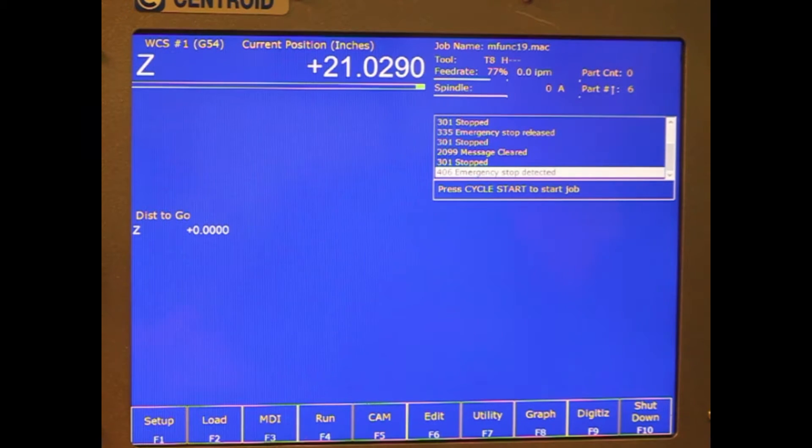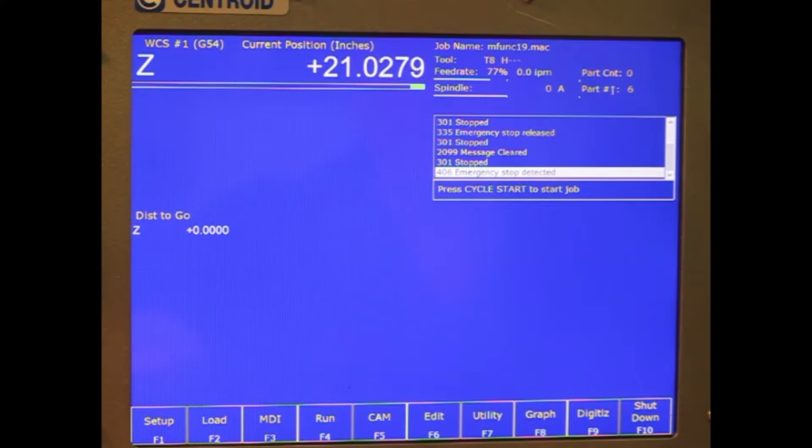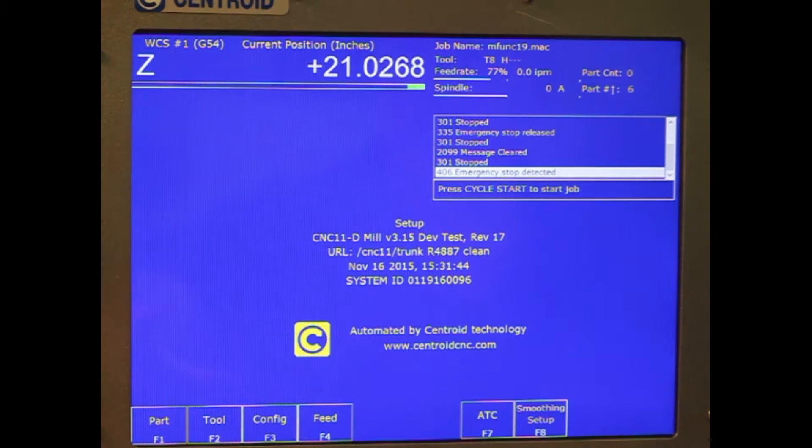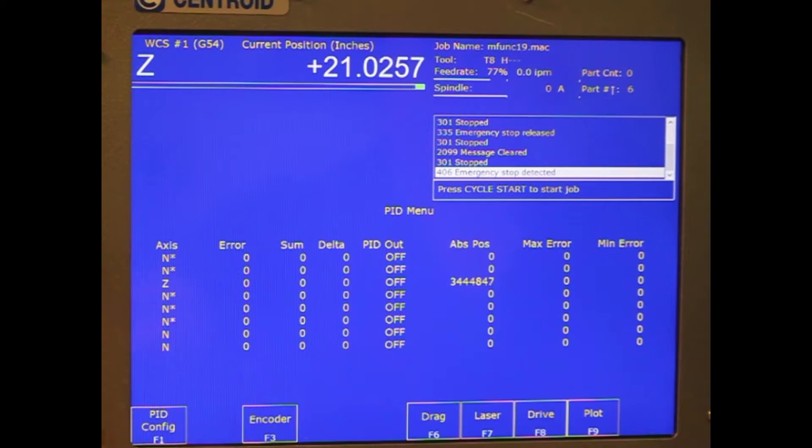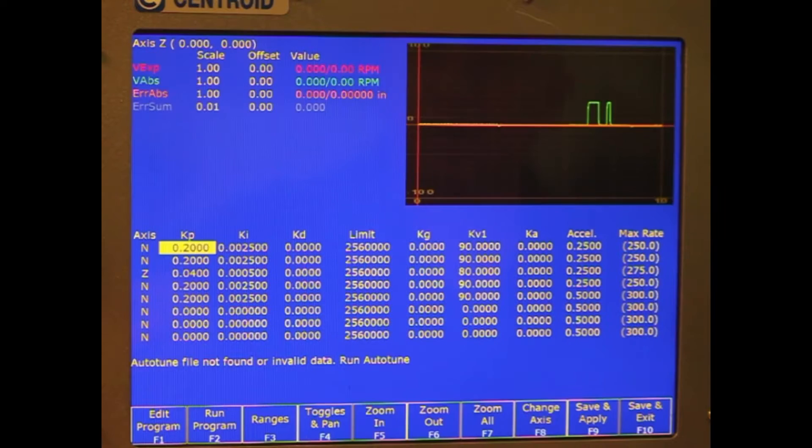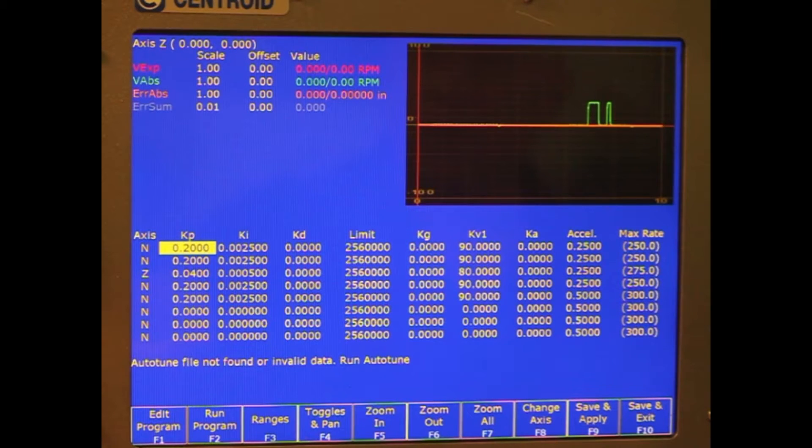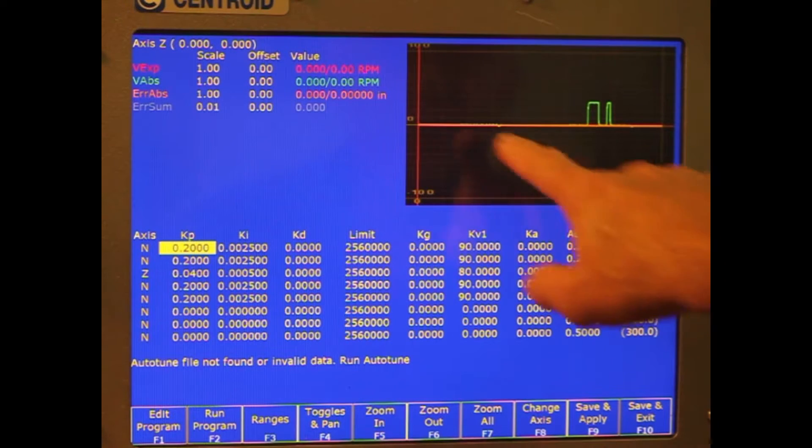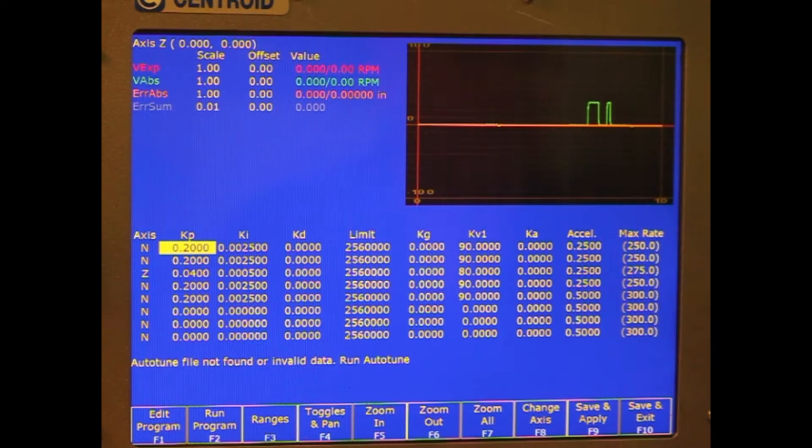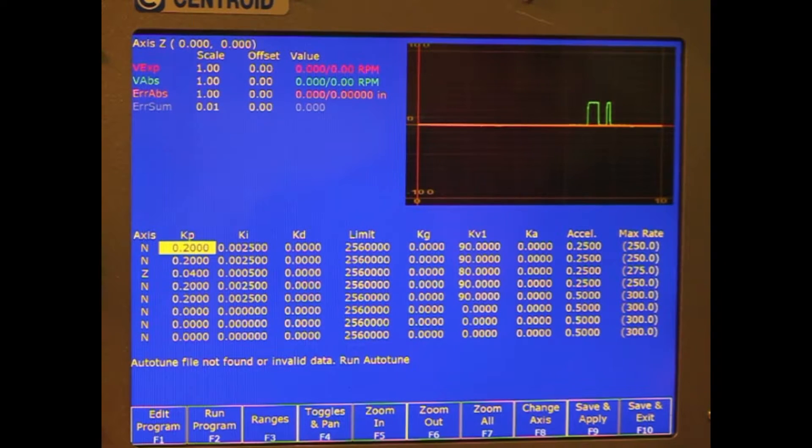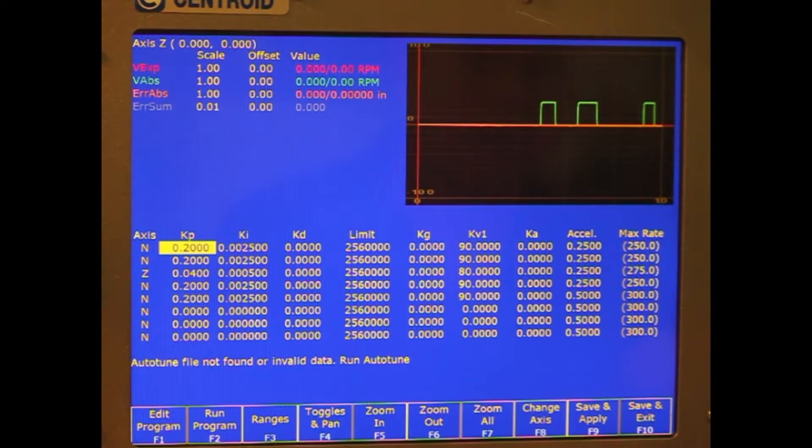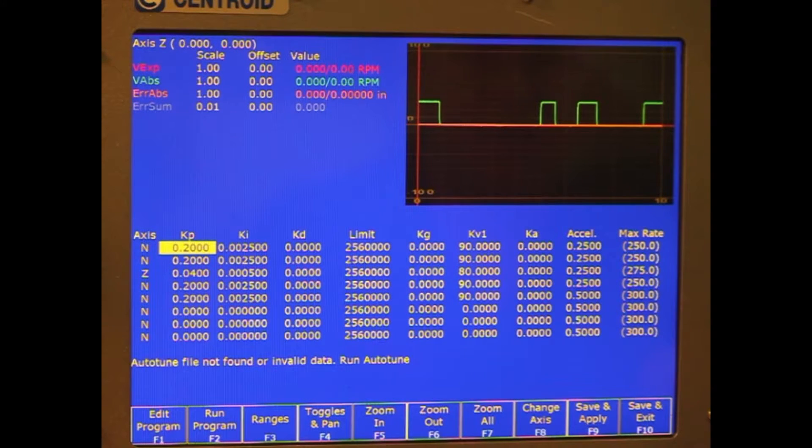Now I'm going to go into the centroid control. I'm going to go into their PID screen. And there's a PID config. You see there's a line graph on here. I can see when I do my step command to the drive, I can actually see the encoder counts generating what would be on the old school servo's tach feedback.